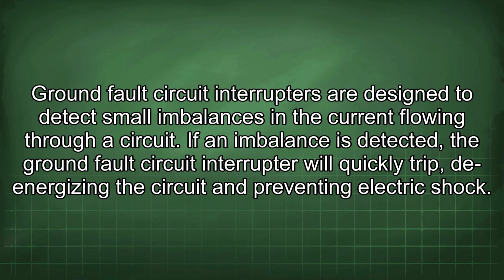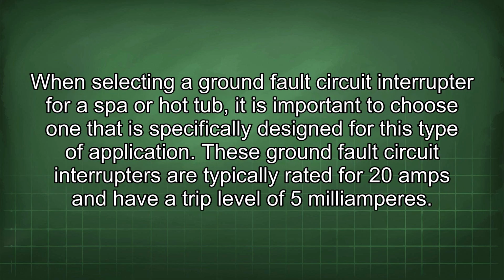Ground fault circuit interrupters are designed to detect small imbalances in the current flowing through a circuit. If an imbalance is detected, the ground fault circuit interrupter will quickly trip, de-energizing the circuit and preventing electric shock. When selecting a ground fault circuit interrupter for a spa or hot tub, it is important to choose one that is specifically designed for this type of application. These ground fault circuit interrupters are typically rated for 20 amps and have a trip level of 5 milliamperes.